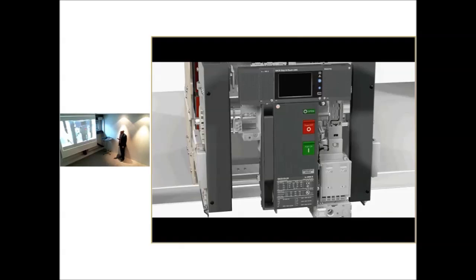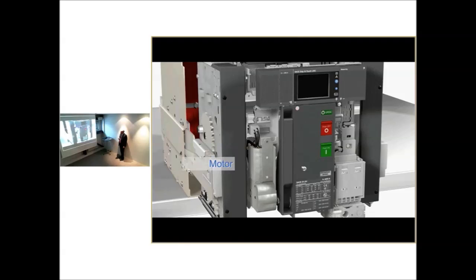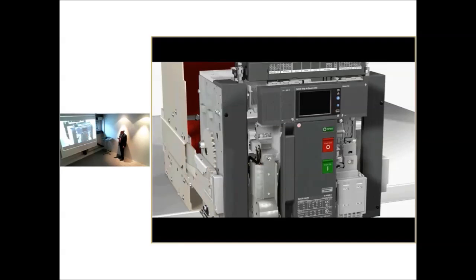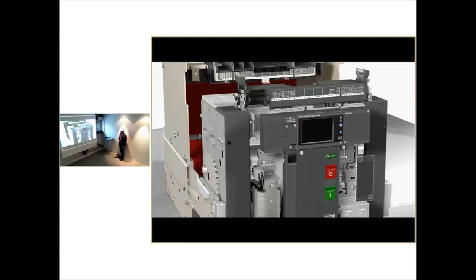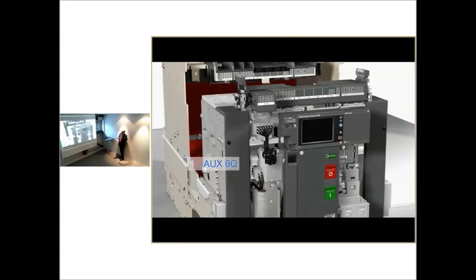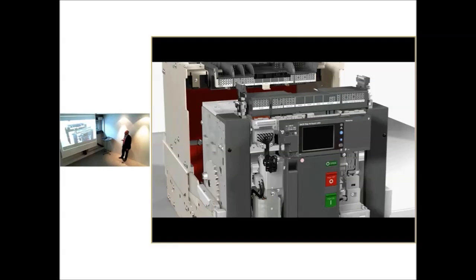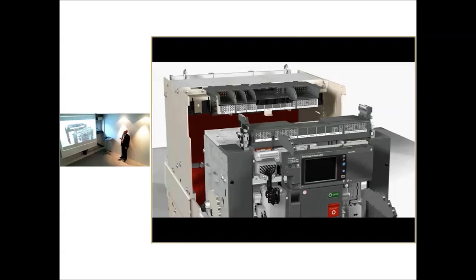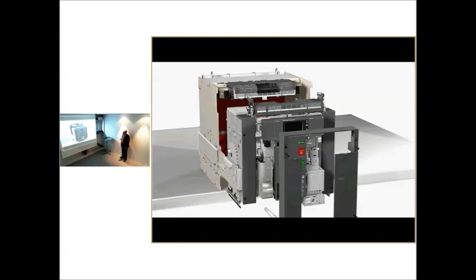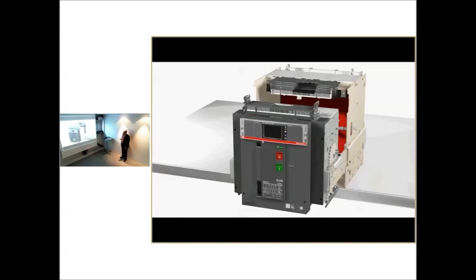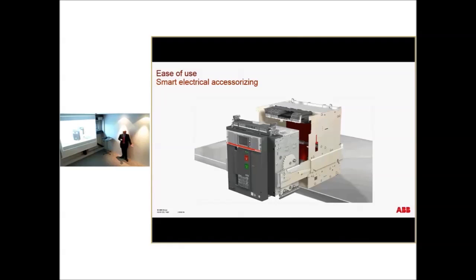On the left side, you have a motor. The motor is also a bit easier. In the front, how to fit: this is a rating plug, and this is external. These are the additional 6 auxiliary contacts, which plus 4 means 10 in total, or they are already inside. These are the Phoenix contacts that you put inside. Then you have a cover and you reclose everything. Right, you see everything is from the front. It is plug-in, you don't need tools, just a screwdriver to put the protection.